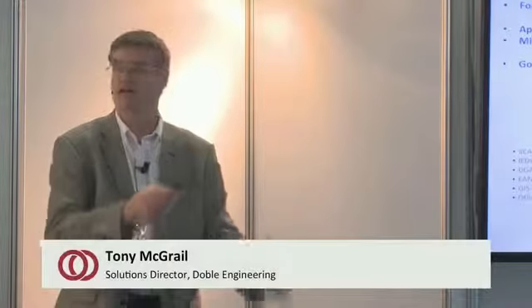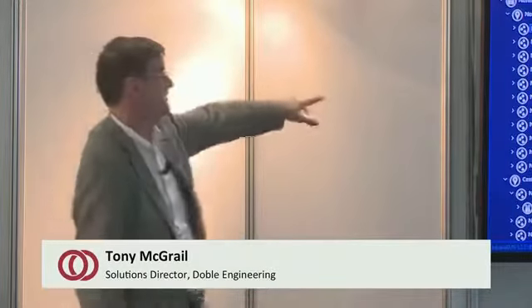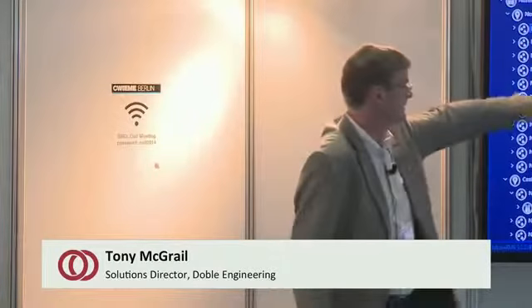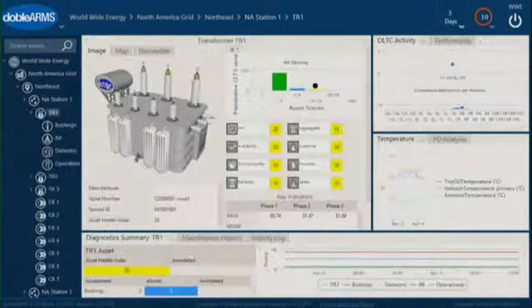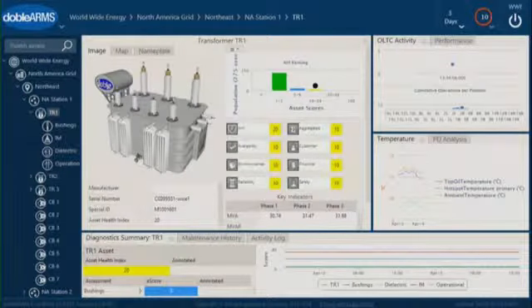Those can be grouped into an assessment. Those assessments will tell you about a logical part of the transformer, and the data has to have relevance. So we can look at one particular transformer and say green good, yellow bad, blue we're not too sure of. But you need to bring all of the data together to give you a risk score, because you may decide that this transformer is in poor condition, but we'll let it fail. That's a decision you can make, which we have made - actively letting a transformer fail.